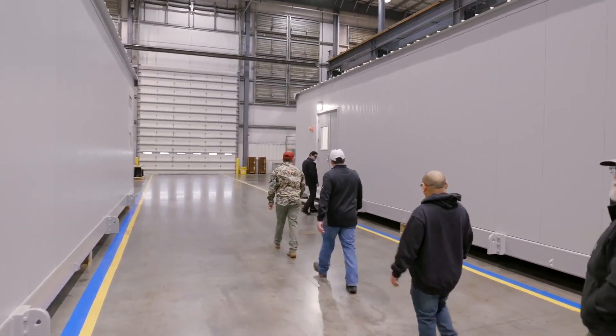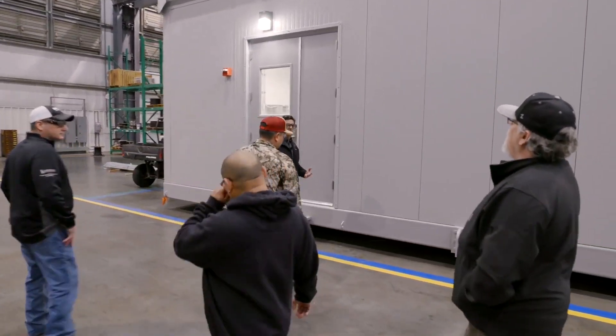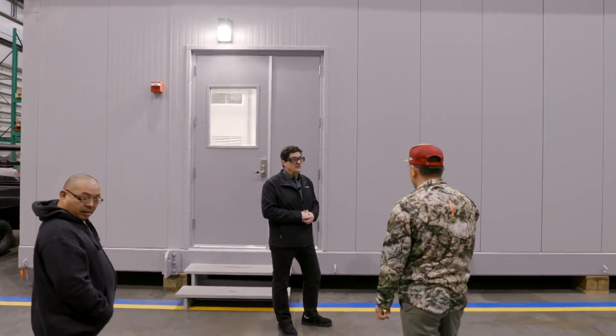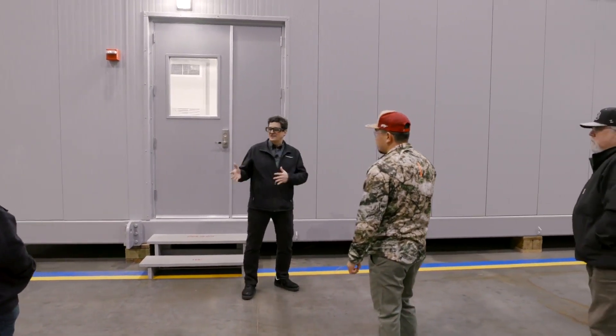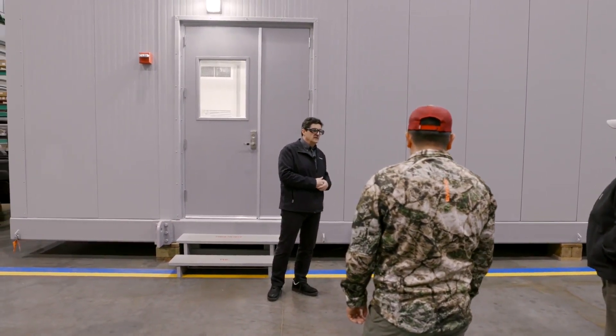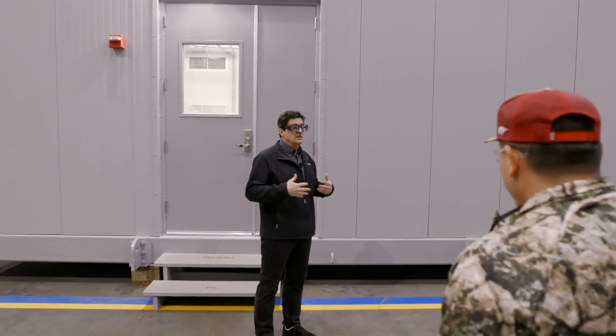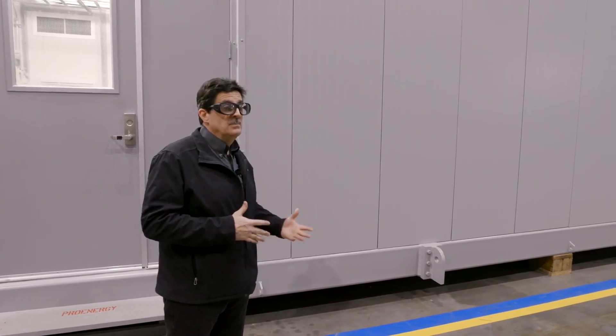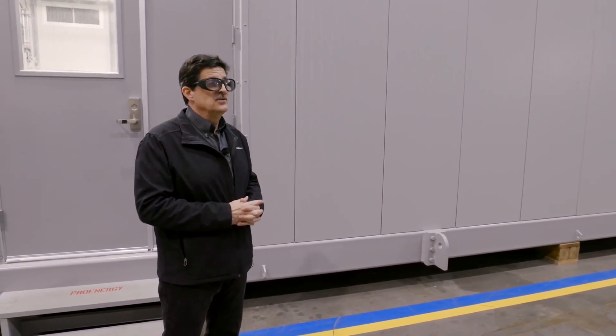You can see the scale of the PDC design — it's a very large tube steel structure. Our standard package is designed for the equivalent of about 180 to 200 mile-an-hour winds and is also seismically rated for California. We build it the same way every time — we don't have a separate seismic package or high wind package. That standardization has allowed us to achieve successful first-button starts, where the first time we push the button the engine starts and goes up with no problem.